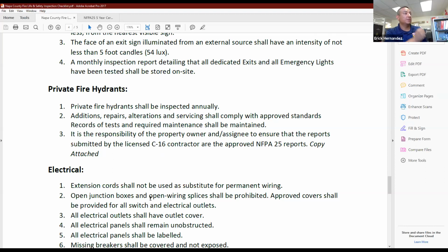And private fire hydrants. All private hydrants shall be inspected annually. If you do have a private hydrant, make sure you reach out to a C16 contractor. The majority of the time, if you have a sprinkler system, it wouldn't be a bad idea to have the same contractor that's servicing your sprinkler system service your hydrants as well. They shall be painted accordingly. Different municipalities have different requirements, but for the county, the requirement is that a fire hydrant shall be painted yellow, and the caps shall be painted depending on what type of pressure you have. If you need help with that, reach out to your C16 contractor, and they can tell you what pressure you have and what color the cap shall be painted.